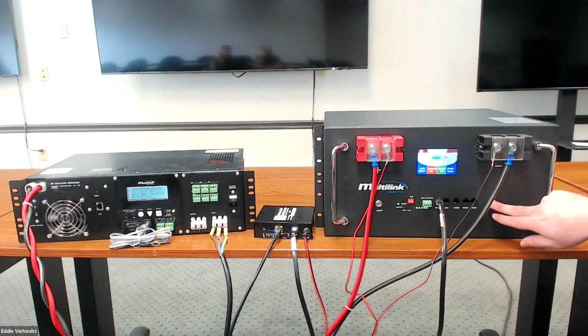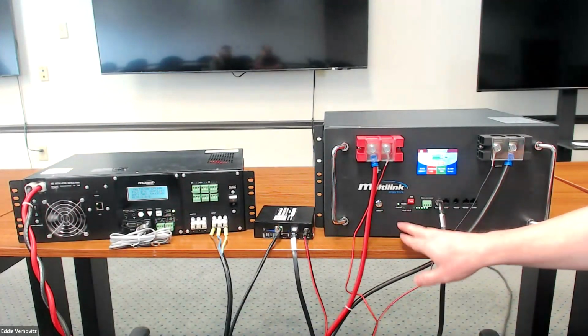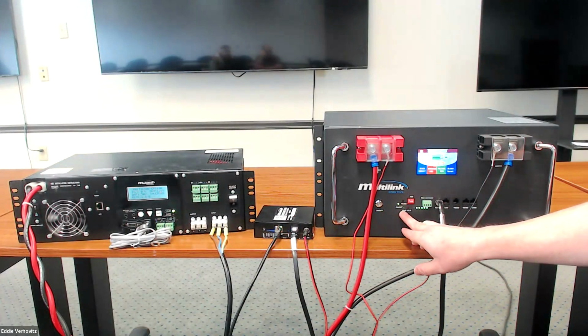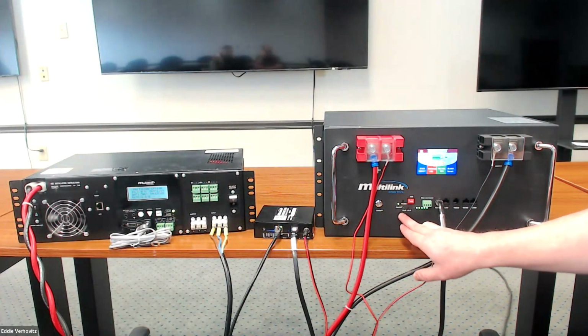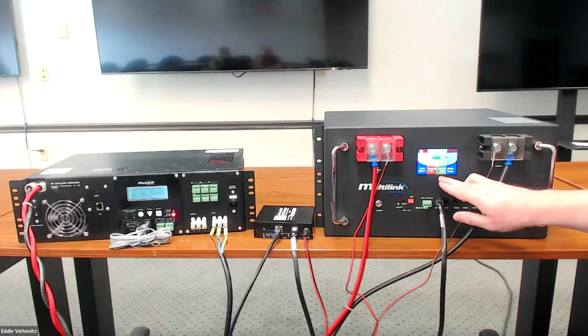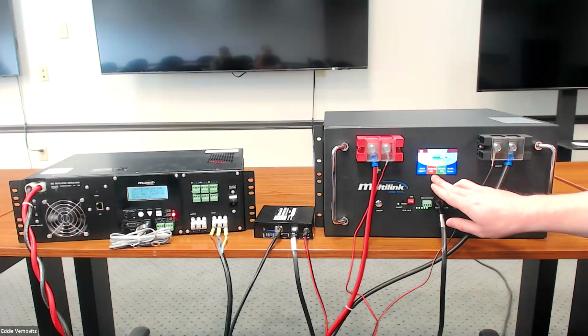The inverter is utilizing the Pantheon cell battery to perform inverting operation and provide 120 volts on its output. During this time, our run LED is now flashing, indicating a state of discharge. If you view this menu, it would also show that we are in a state of discharge, currently drawing about 1 amp of current.